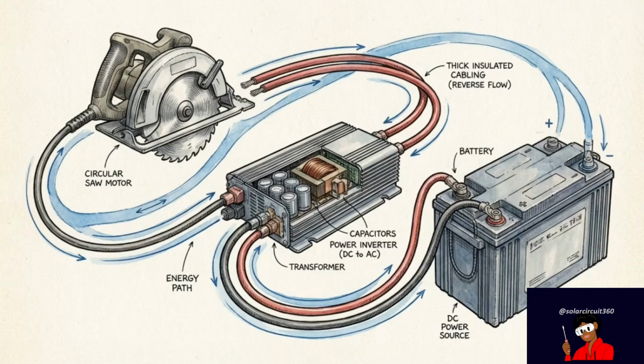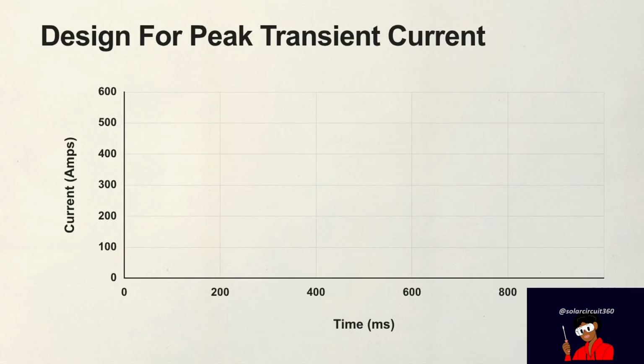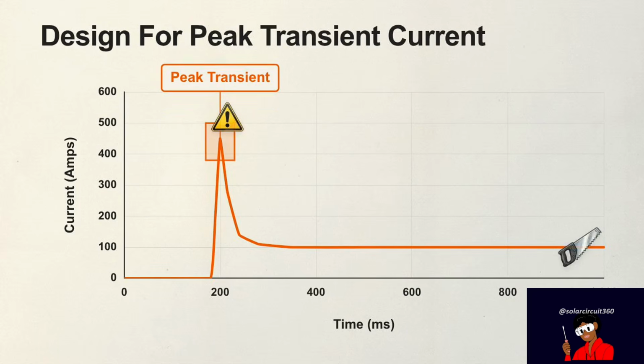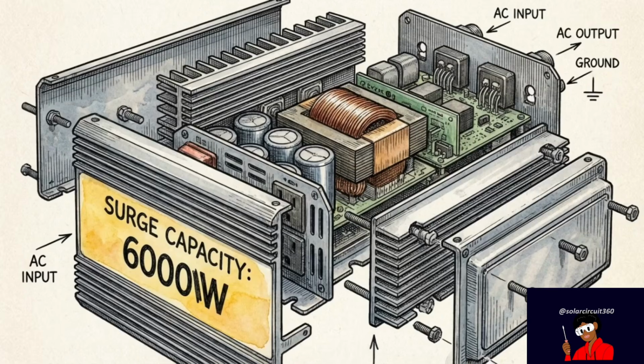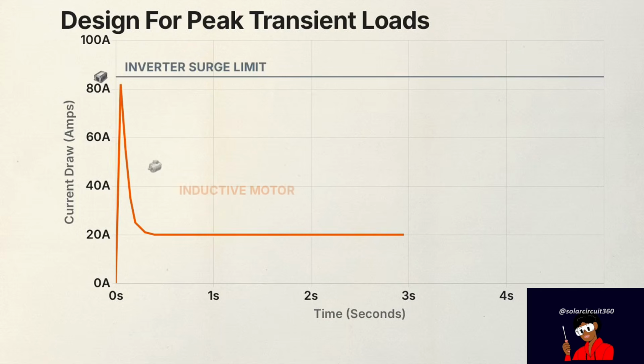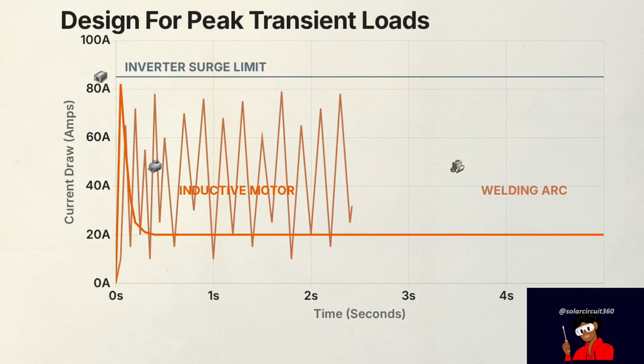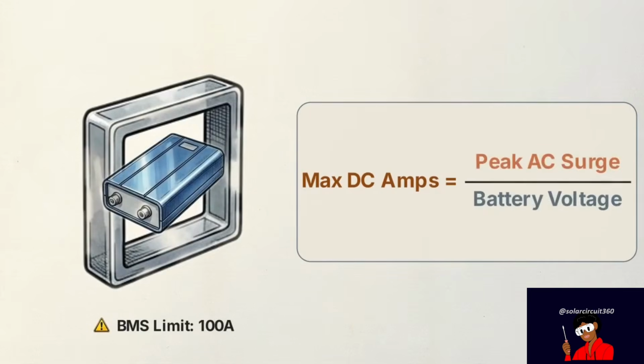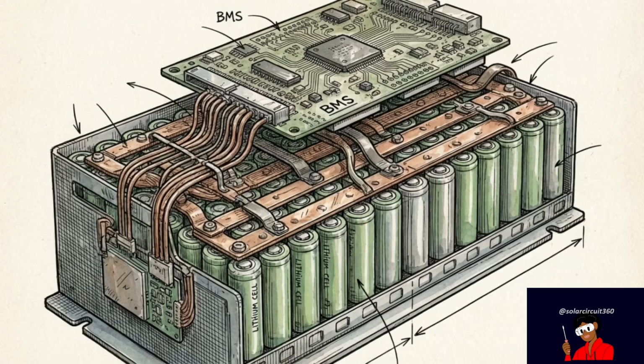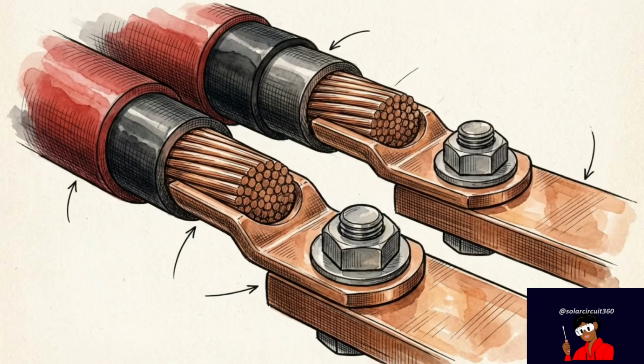We can now view this entire electrical path as a single, connected ecosystem. Safe off-grid design requires sizing every component for the absolute peak transient current, rather than the best-case continuous average. The first design step is oversizing your inverter specifically for surge capacity. You must account for the high starting spike of an inductive motor, or the chaotic demands of a welder. The second step is calculating the exact maximum DC current draw. You have to verify that both the battery's chemical discharge rating and the hard limits of its internal BMS can survive that mathematical spike. Finally, you must utilize heavily oversized cables to minimize resistance, eliminate thermal hazards, and prevent the voltage drops that crash systems.